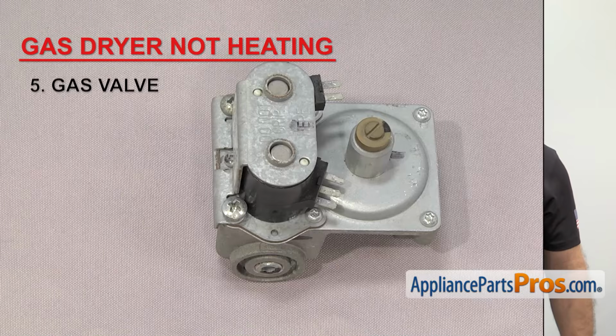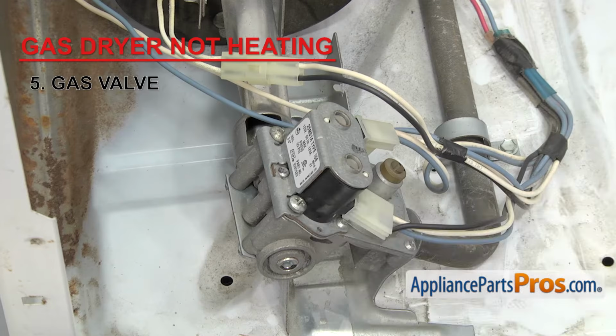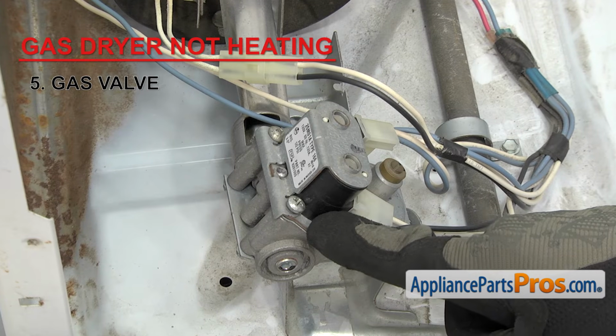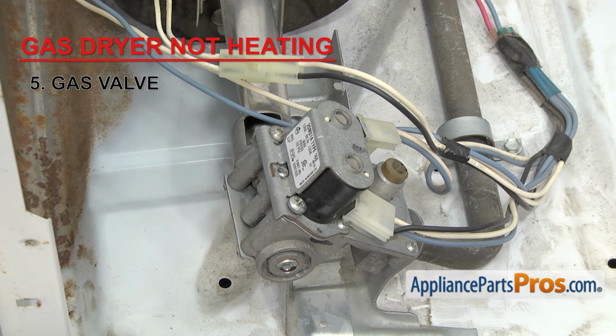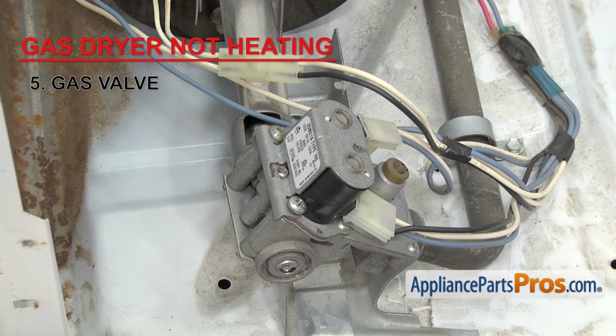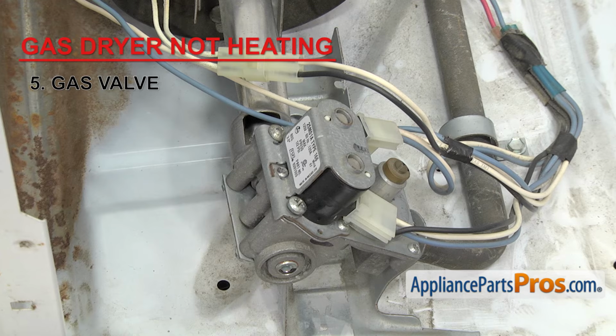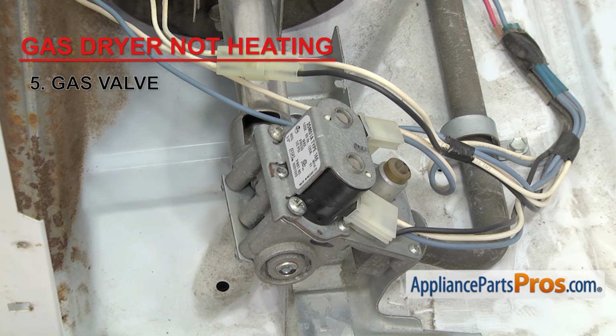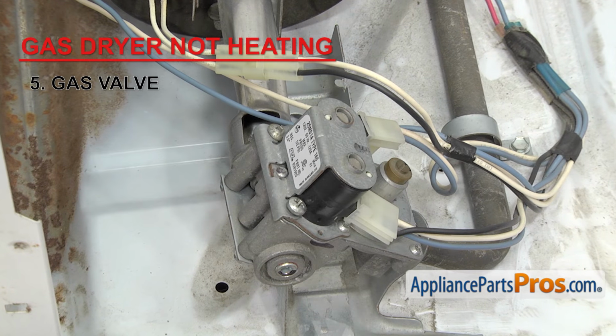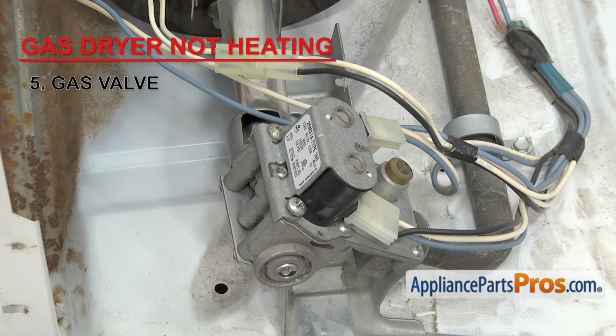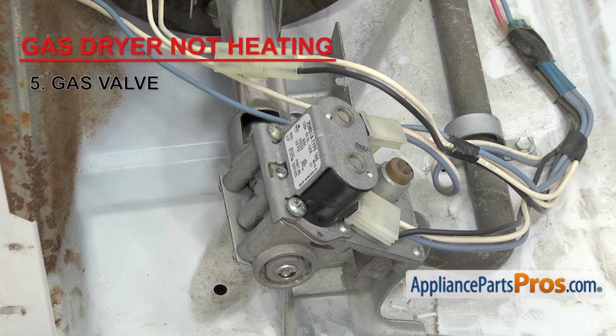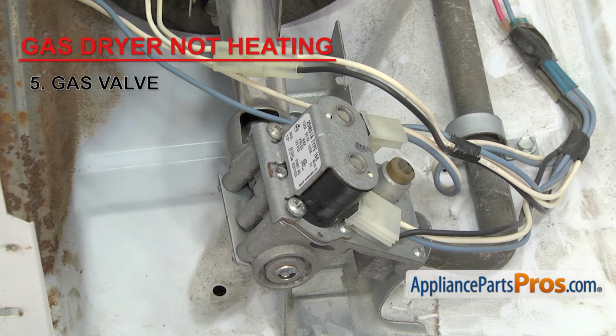The last thing to check is the gas valve. It lets the gas into the burner. It's usually located by the burner assembly. It's unusual for this part to fail. If it does, it's either because it's stuck open and gas is leaking out, or it's stuck closed and no gas can get through. If you've already checked everything else and there are no loose wires, but the gas valve still isn't opening, or it's leaking, then it needs to be replaced.